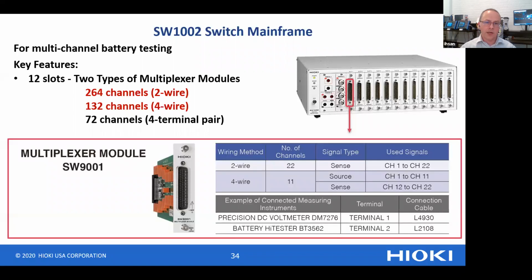Now for multi-channel battery testing, let's say you were testing 10 sites or 12 sites. It's more cost effective to have a single instrument and test sequentially one after another rather than have 10 instruments. So we have this solution called the SW1002, which is basically a multiplexer which accepts 12 multiplexer modules. It comes with two different styles of multiplexer module. The SW9001, with all 12 slots populated, gives us 264 channels of 2-wire or 132 channels of 4-wire.